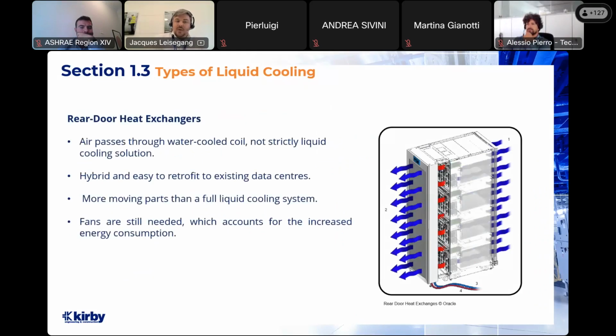And lastly, as I said, rear door heat exchangers. The rear door heat exchangers are not strictly liquid cooling. Your coolant is still piped into the data hall, but it's piped into a coil which sits on the rear of your rack. The cold air is drawn into the front of the server, and the heat is removed directly at the rack. Although this is not strictly a liquid cooled solution, it is being looked at because of the increased rack density you can achieve, and the fact that it's easy to retrofit into existing data centers. Fans are still needed, and that accounts for the increased energy consumption and the lower energy efficiency compared to a full liquid cooled system.